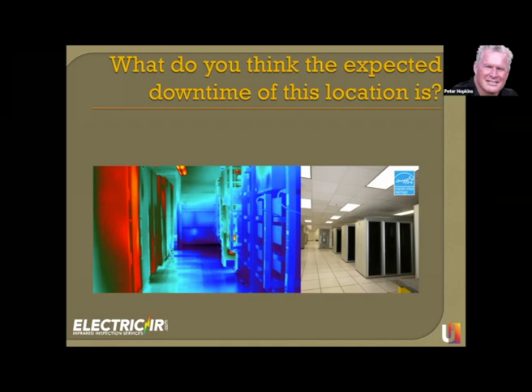That takes time. But this particular connection fed what's called a rectifier, which is involved in converting DC to AC to power the equipment, or AC to DC. So they start in main switchgear with what's called an ATS, an automatic transfer switch, with a main breaker, so that if power is ever interrupted from the utility provider, the ATS switches over to a generator, usually within split seconds.